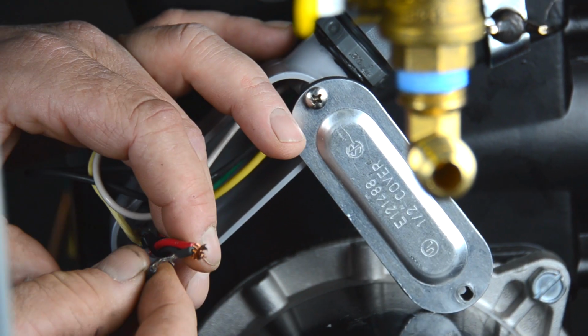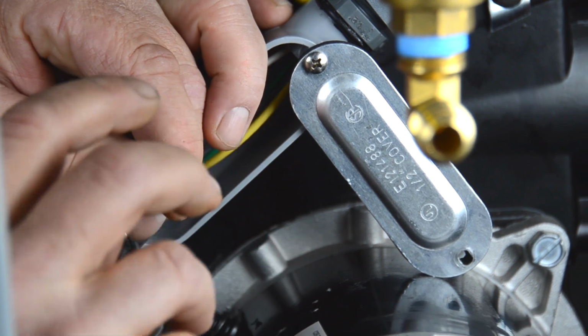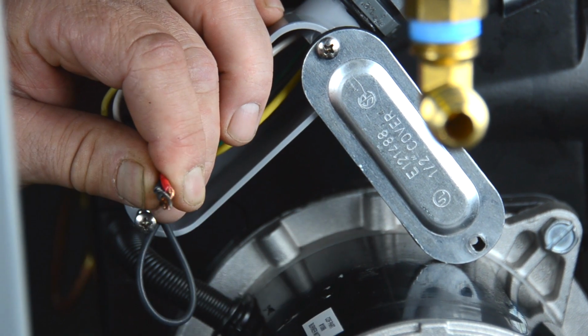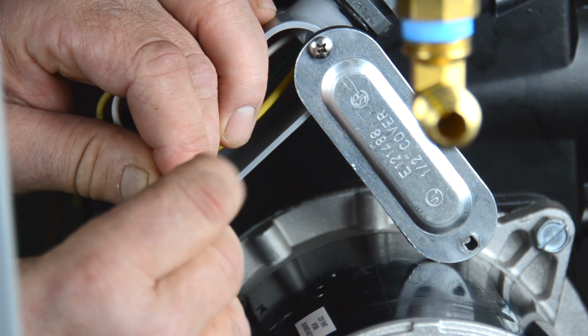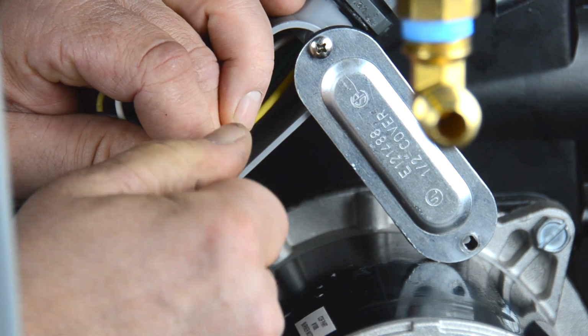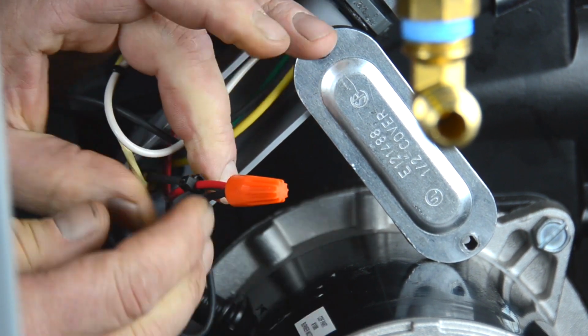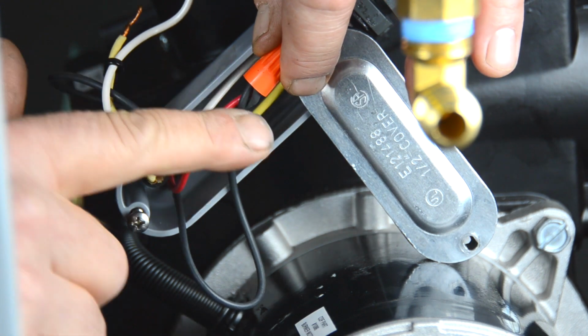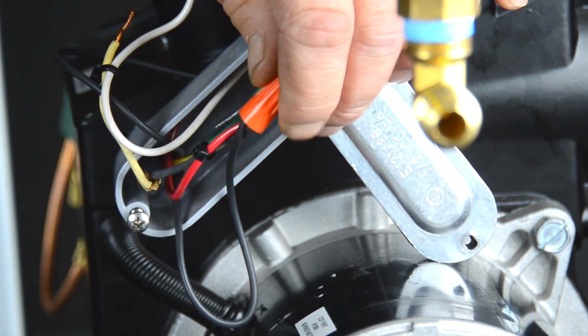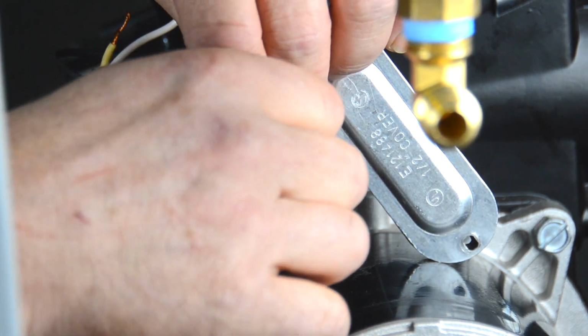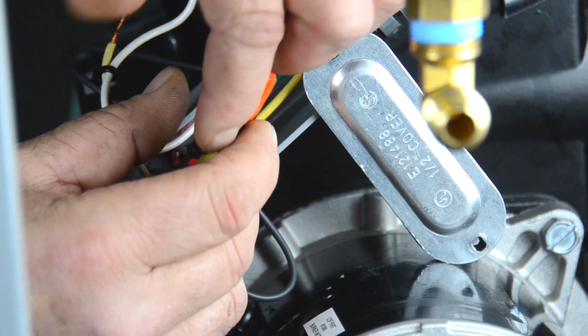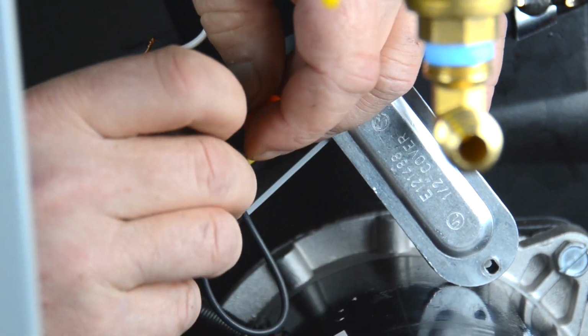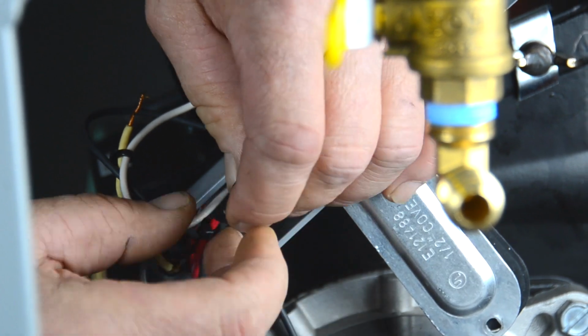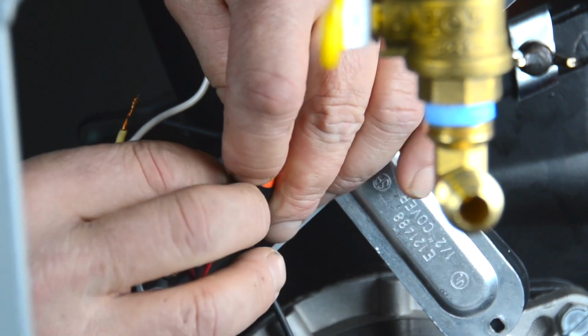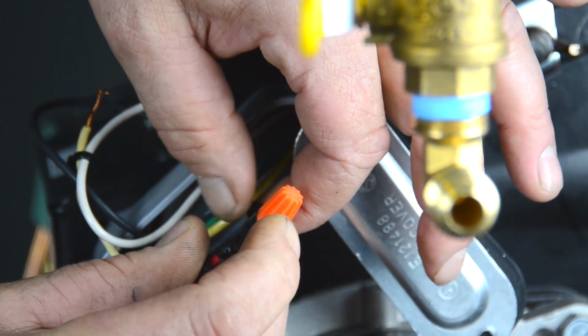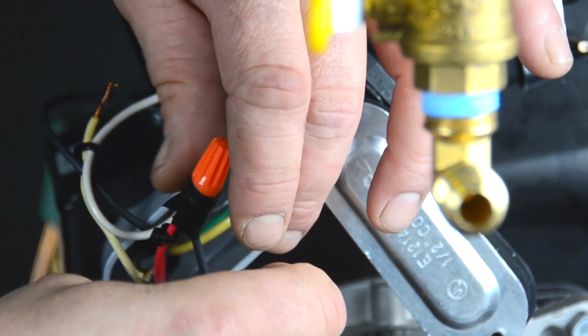Then take a transformer wire, one of them, twist it in. You're going to wire nut that so that you get a transformer, a burner, and your power wire. Right here, two blacks and a red. Always make sure you tape your wire nuts. That's as much for vibration as it is for safety. Make sure that your connections don't come apart. I always fold the end of the tape over so we can get them off again.